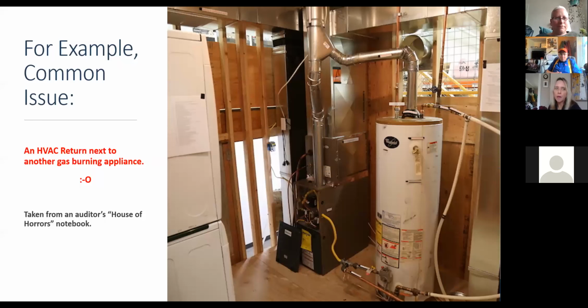Just an example here, this is not my photo, but it's from an auditor's House of Horrors notebook. An HVAC return right next to a natural gas burning water heater with an open flue cap. So this flue sitting on top of the water heater, you have to test that for what's called spillage, if air is spilling out and not just going all the way up the flue. This flue is not to code. You can see in the picture it actually declines once it goes up, and the ductwork is arching over the entire water heater.